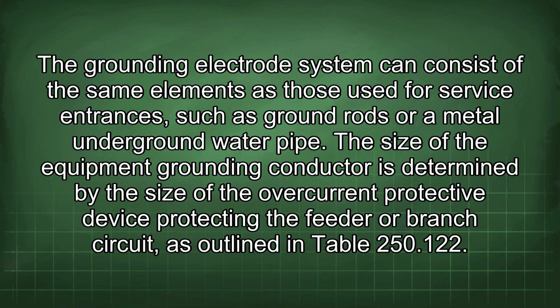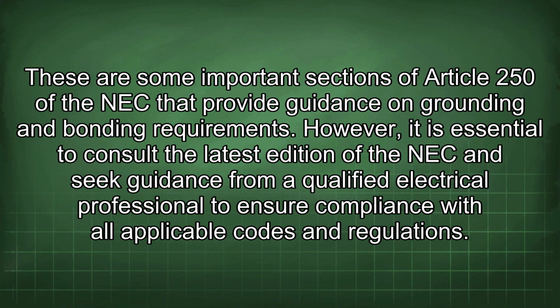The size of the equipment grounding conductor is determined by the size of the overcurrent protective device protecting the feeder or branch circuit, as outlined in Table 250.122. These are some important sections of Article 250 of the NEC that provide guidance on grounding and bonding requirements. However, it is essential to consult the latest edition of the NEC and seek guidance from a qualified electrical professional to ensure compliance with all applicable codes and regulations.